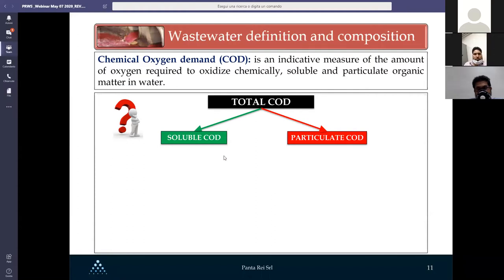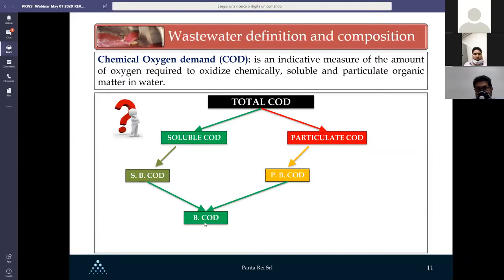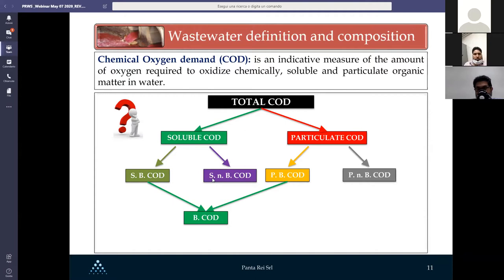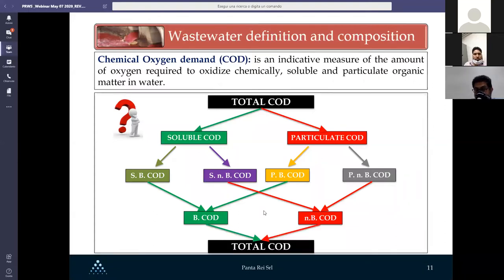The total COD consists of soluble COD and particulate COD. We also have soluble and biodegradable COD, and particulate and biodegradable COD — summing these two fractions gives the biodegradable COD. Similarly, soluble non-biodegradable COD plus particulate non-biodegradable COD gives the non-biodegradable COD. Together, biodegradable and non-biodegradable COD make up the total COD. Pay attention: when we say COD, which fraction are we actually referring to?